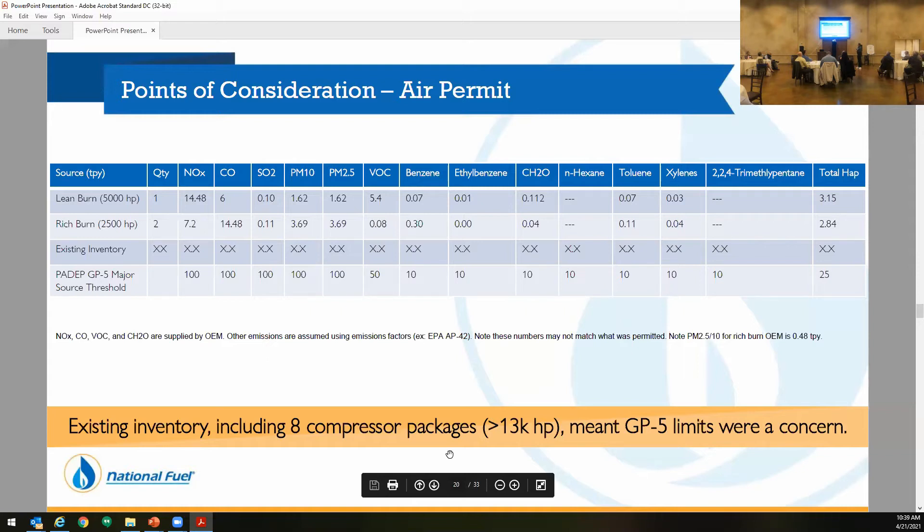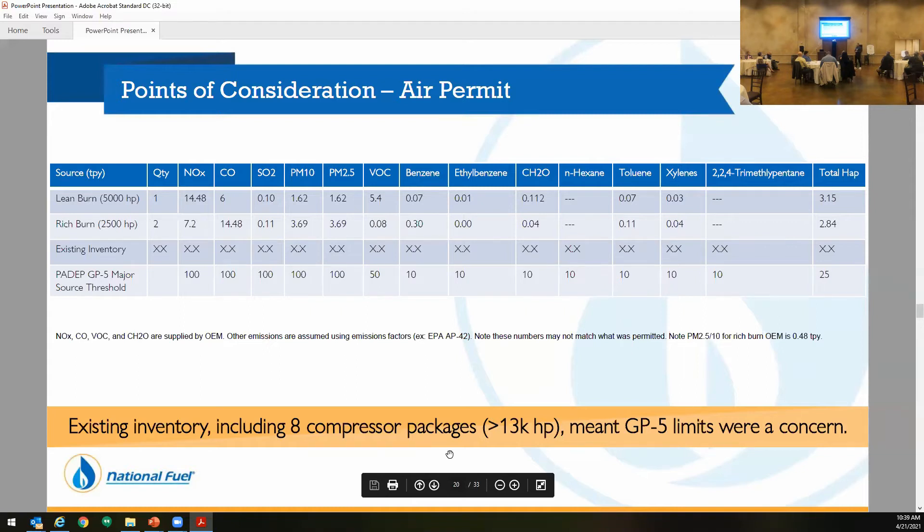Second was the cost of all the equipment. I didn't put the actual cost just to keep it from the various packagers. The most expensive option was going with the 2,500 horsepower units that we owned, using an engine-driven cooler, because we didn't own those coolers and we'd have to change some things on the unit. Option one — even though we owned the units — we had significant changes: they were only single-stage, so we'd have to convert them to three-stage and change the coolers. Third place was two 2,500 rich burn units with two engine-drivens at about 80% of total cost. The cheapest option, which makes sense since it's half the equipment, was going with the one 5,000 horsepower lean burn. Most people right now are saying this is a no-brainer — why aren't we just going with that option?